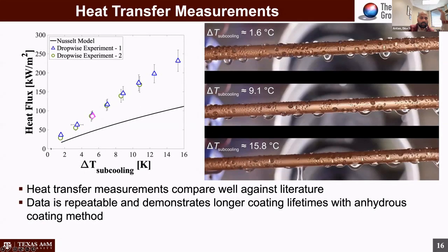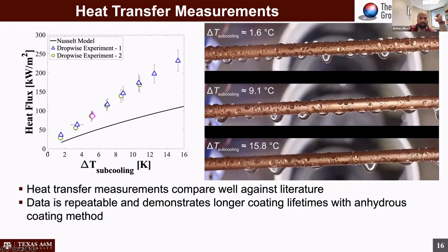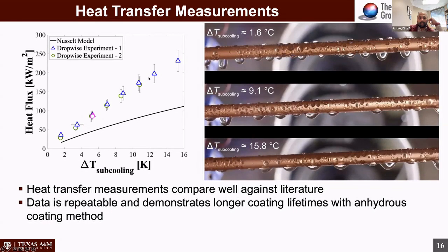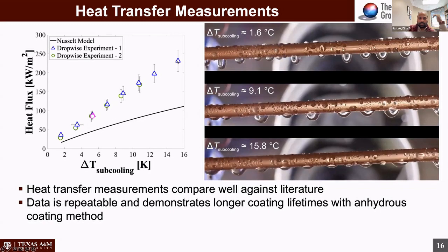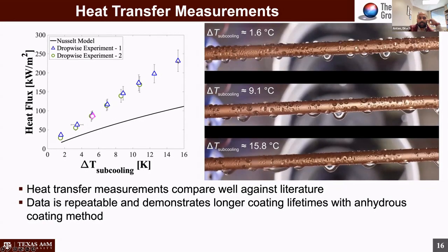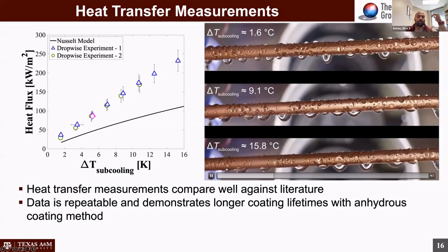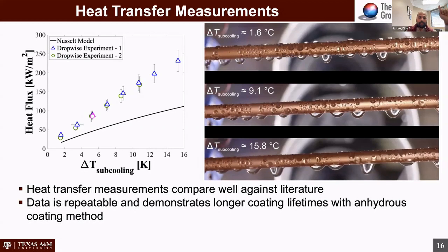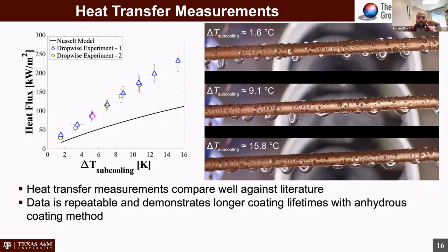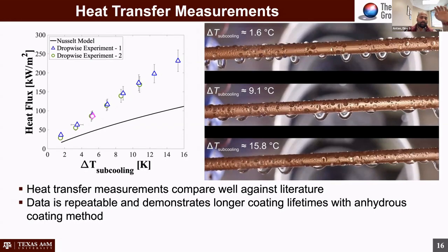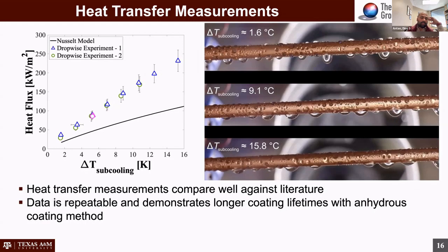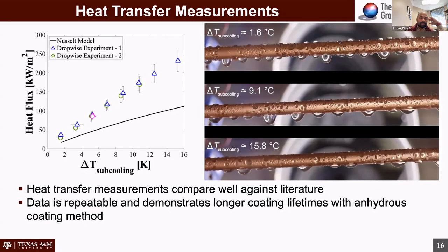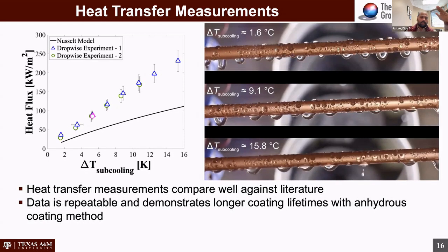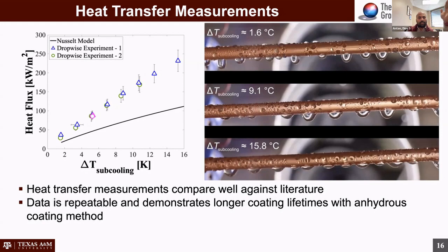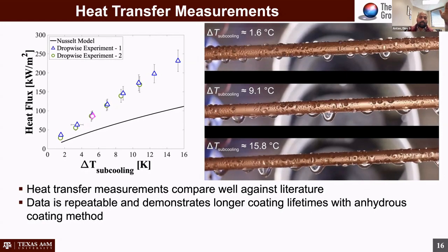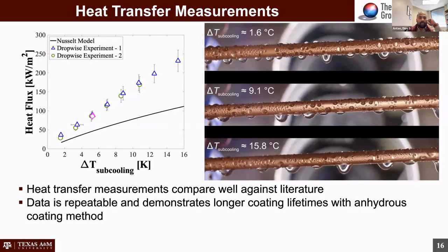And so a typical experiment, for those of you who do condensation work, is we start at the lowest subcooling and we increase subcooling right up to the point where the system cannot maintain steady state anymore. And so we collect the heat flux data as a function of the subcooling. What you'll observe in the plot on the left is 2 data points that are in pink compared to the rest. And those data points were actually taken after we finished the entire experiment. So the experiment lasted about 4.5 to 5 hours on average. So we stepped up the subcooling, collected the heat flux data. And after the entire experiment ended, we went back and reduced the subcooling and collected data again at one of the low subcoolings. This tells us 2 things.